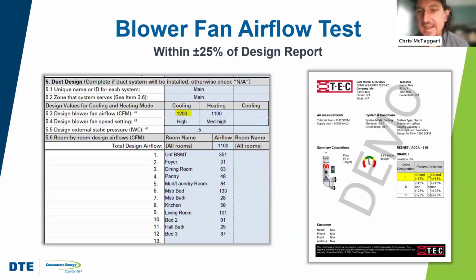Again, we could be all the way down to 25% less. So potentially a more significant variation could be permitted. Obviously, we would prefer not to have a big variation, but 25% of 1200 gives us 300. So we could be all the way down to about 900 CFM and technically still pass. Obviously, we're happy to have something that performs better.